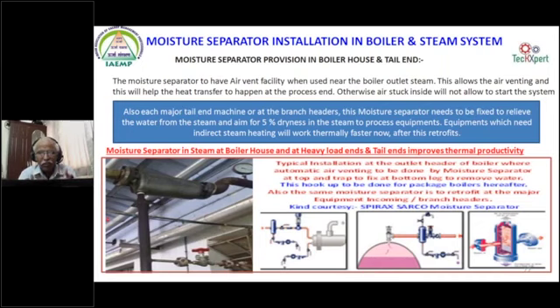Once we monitored and measured, we gave it to them for correction. They have gone for an excellent flow meter with steam dryness compensation, and it is able to measure the dryness from the flow meter also: a steam flow meter with steam dryness measurement. The next is on all the equipment at the incoming side, so that at the boiler they have an air venting provision, so that the air is vented out from the moisture separator. At the equipment, air need not be vented, but water has to be removed before entering the equipment. The thermal productivity of the equipment goes up very well.